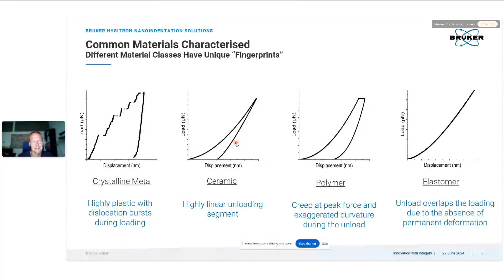So this is the most influential parameter, and basically what that also means is that the reduced modulus is given by the slope of the unloading segment, so how the material is pushing back the tip when you are unloading, and the hardness is simply the maximum force divided by the contact area. So we need to produce some deformation to the material to actually get the hardness properties right. But I'll talk about that later. But the most important thing is that we are penetrating into the material and we are collecting load and displacement data. And if you look at these indentation curves on the different materials, you might already get the idea what the material is about. So if you look at the crystalline metal, you see the discontinuities that are related to the plastic deformation. So we see some elastic deformation in the beginning, and then this material starts plastically deforming. The other materials have a different shape of the unloading segment, which results in a different value of the elastic modulus.